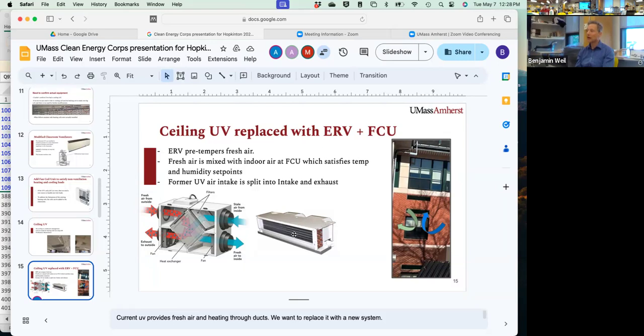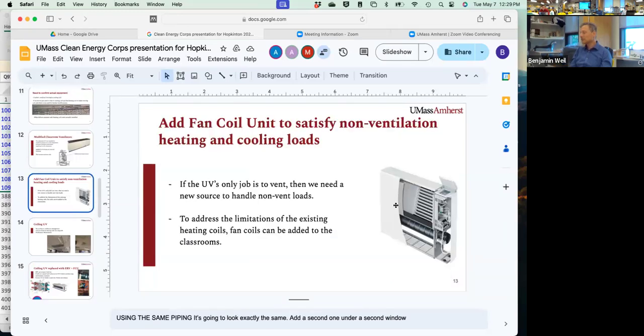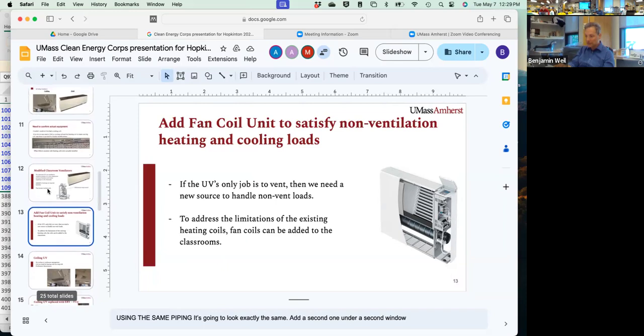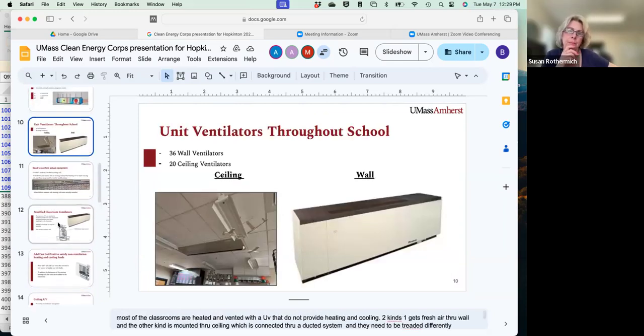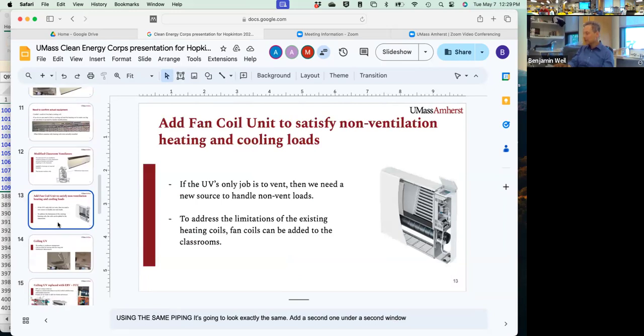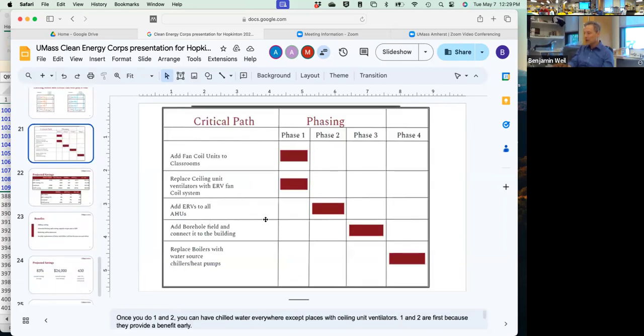It's fairly simple to specify. Probably if you've got a contractor that you typically work with on HVAC stuff, you could get them to do some so-called shop drawings to spec it out, because it is pretty simple, and then price it, and that would be a way to budget for these. If it turns out that there are not actually cooling coils in those unit ventilators, then we're talking about specifying a fan coil unit for each of the 36 classrooms, is it? Yep. Yeah. That would need those. But again, that gets you to cooling. So that seems like a good first step.